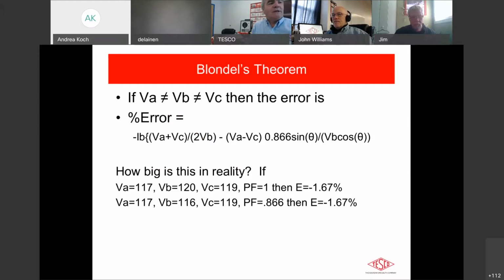All right. So the calculation is there on line 3, but what does that really mean? What that really means is, let's say we had VA was 117 volts, VB was 120, VC was 119. Okay. That seems like something that you might see out there. That's pretty good, actually, right? You got a power factor of 1. That's extremely good. So everything looks good. My meter is perfect. Everything's right. And yet I am getting an error of almost 2%. All right. So we've got a bit of an issue here. Keep going, John.